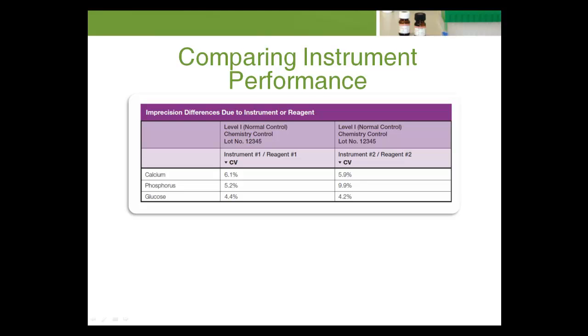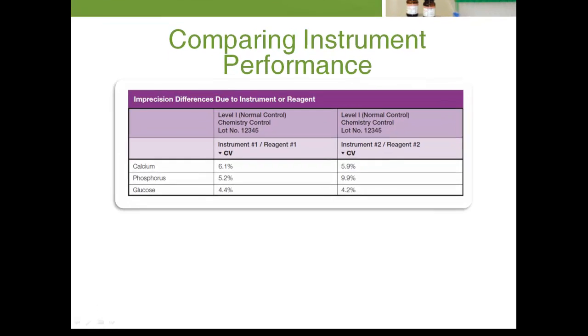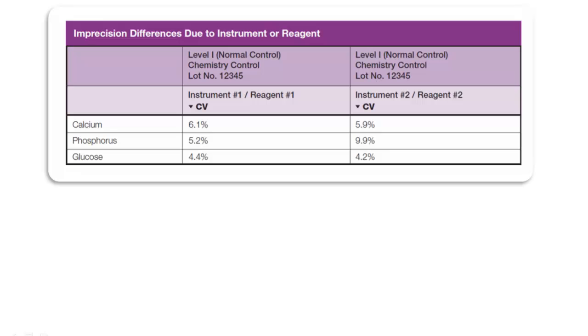The coefficient of variation can also be used when comparing instrument performance. In this example, instrument 1 and instrument 2 have similar precision for calcium and glucose, but instrument 1 demonstrates much better precision than instrument 2 for phosphorus. Because the precision was calculated from data for the same lot number and level of control, the differences in precision are likely due to the instrument or reagent.